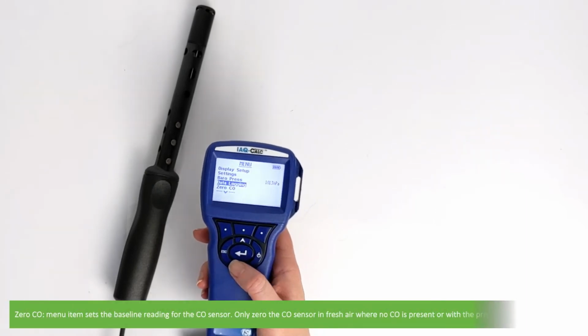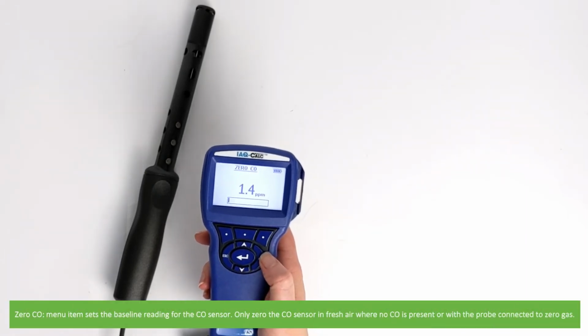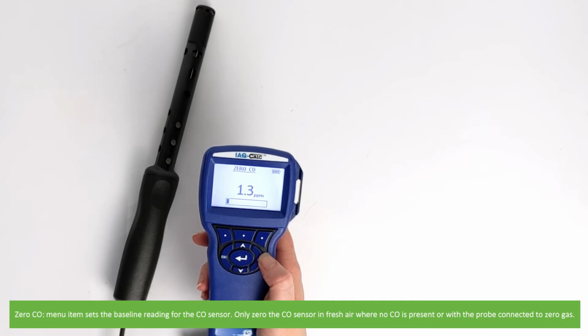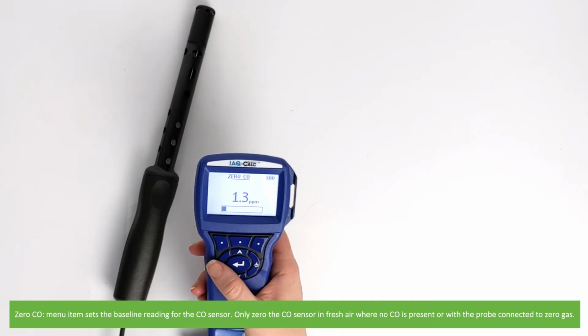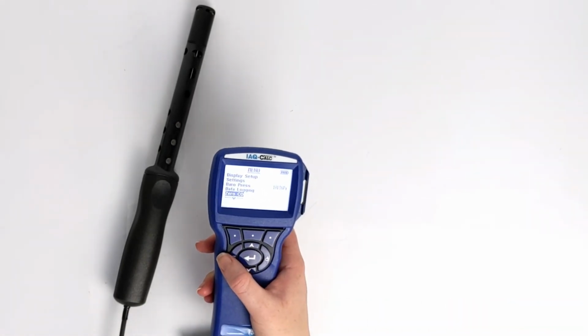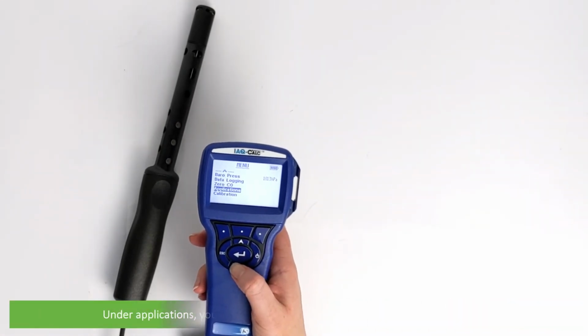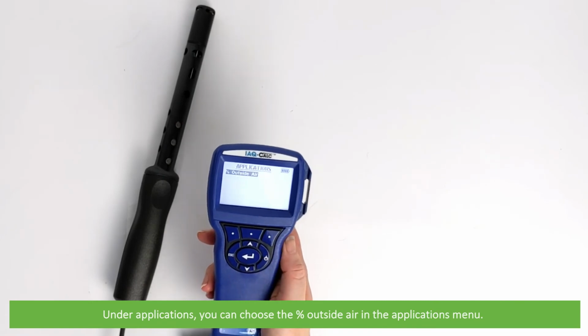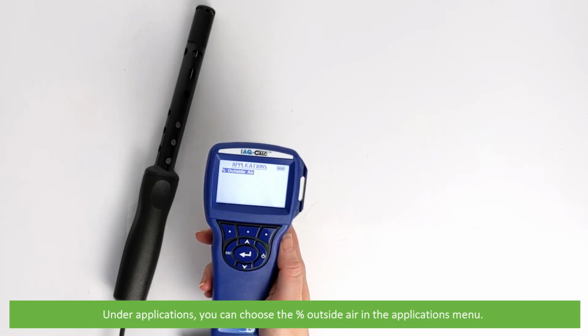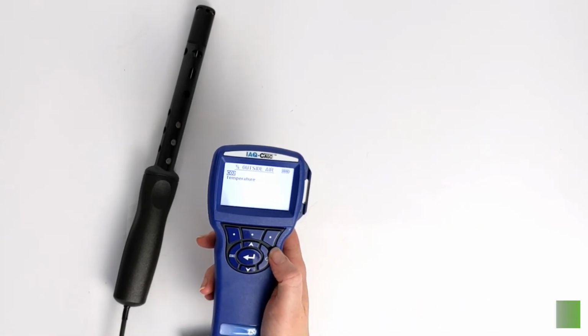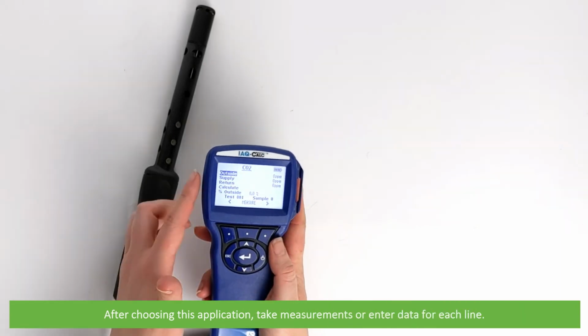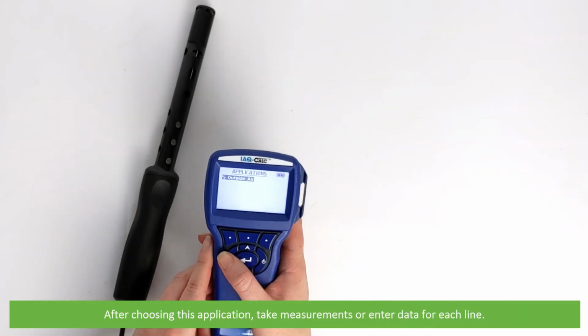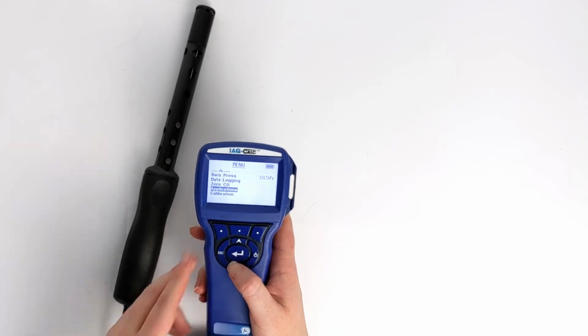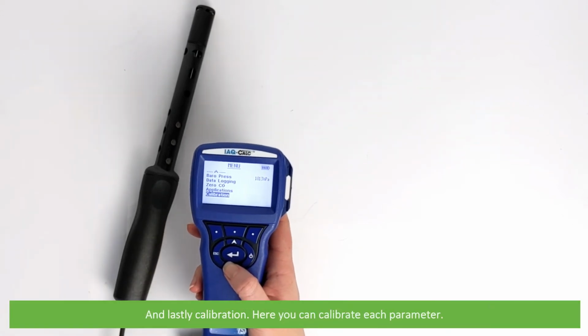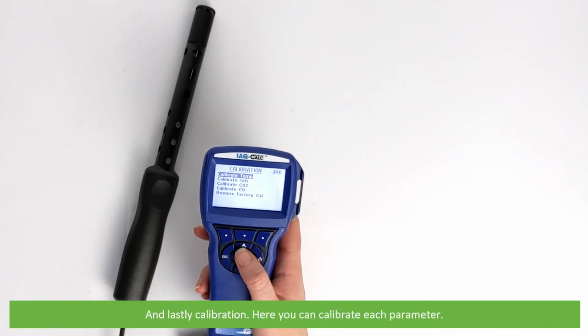Zero CO, this menu item sets the baseline reading for the CO sensor. Only zero the CO sensor in fresh air when no CO is present or with a probe connected to zero gas. Under Applications, you can choose the percentage outside air in the application menu. After choosing this application, take measurements or enter data for each line. And lastly, calibration. Here, you can calibrate each parameter.